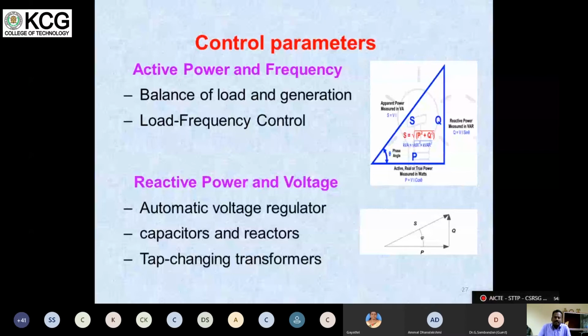So load frequency control is done with active power, that is, the prime mover system. In a thermal power plant, the prime mover is the turbine. By opening or closing the governing system, we can control the frequency. What is frequency? Frequency is nothing but the speed of the turbine. So if we are able to control the speed of the turbine, then frequency can be maintained. According to the load, we have to regulate the governing system valve to open or close to keep the speed constant, that is 3000 RPM. Then we can maintain the frequency at 50 Hz in the system.